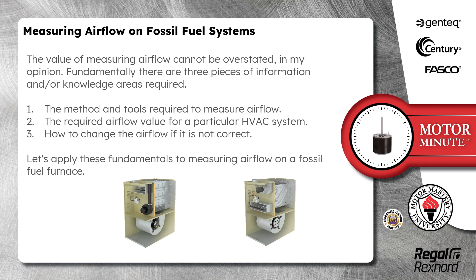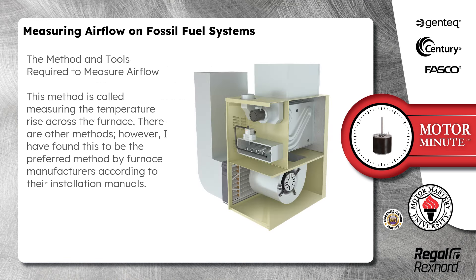Let's apply these fundamentals to measuring airflow on a fossil fuel furnace. This method is called measuring the temperature rise across the furnace. There are other methods; however, I have found this to be the preferred method by furnace manufacturers according to their installation manuals.